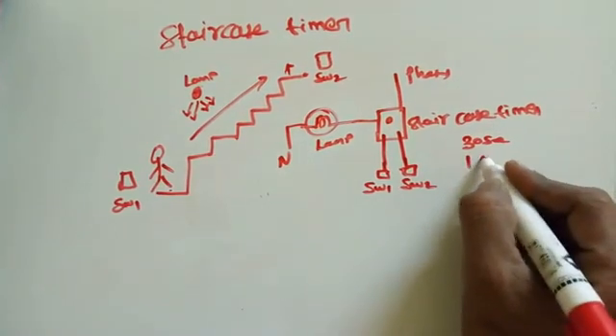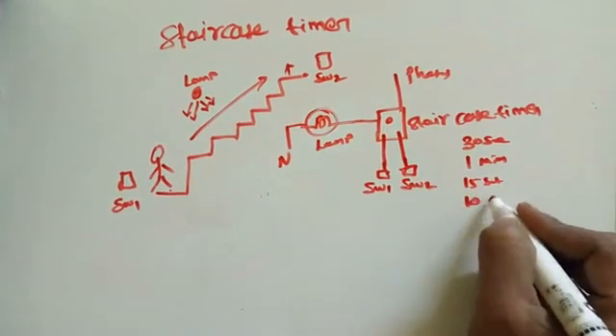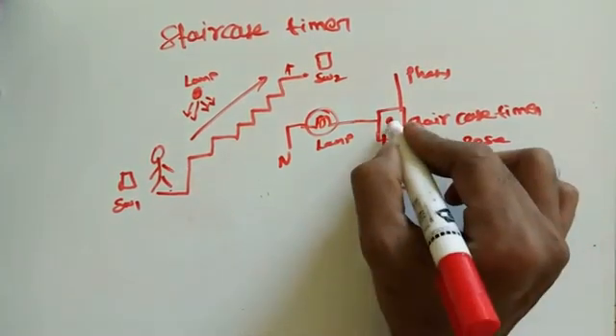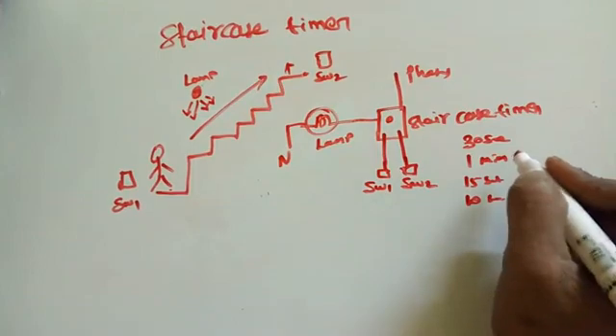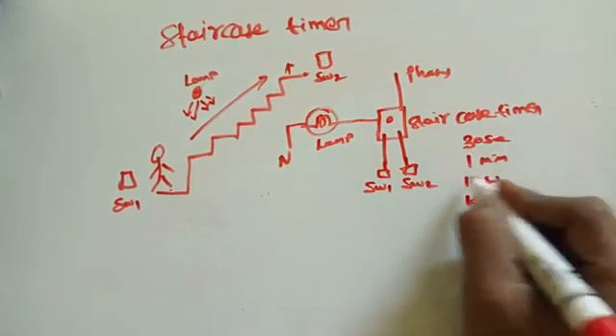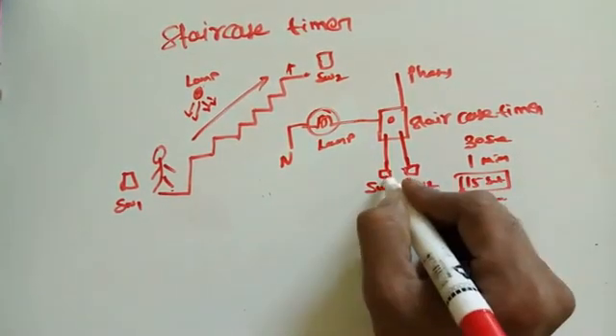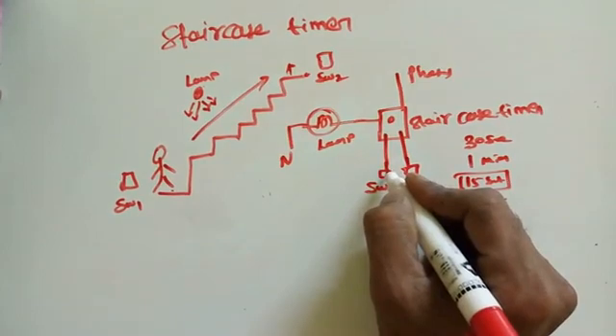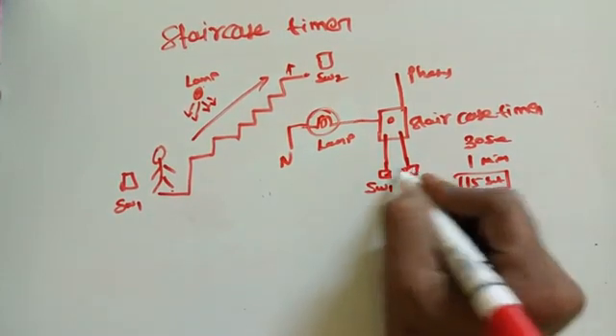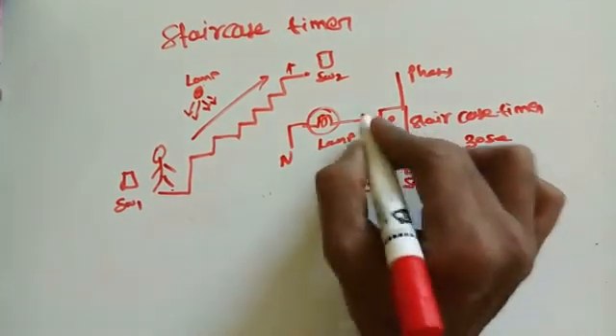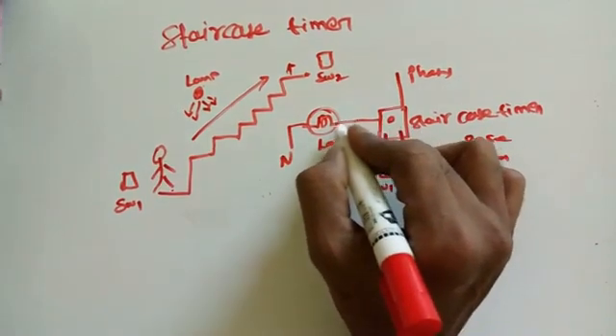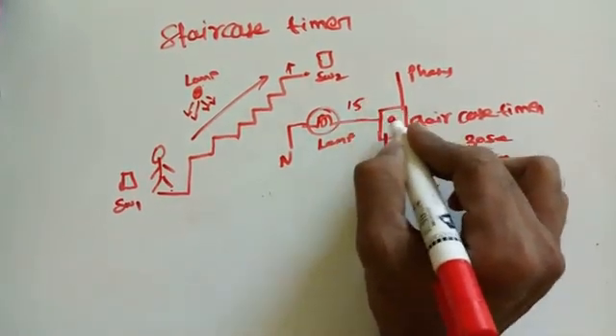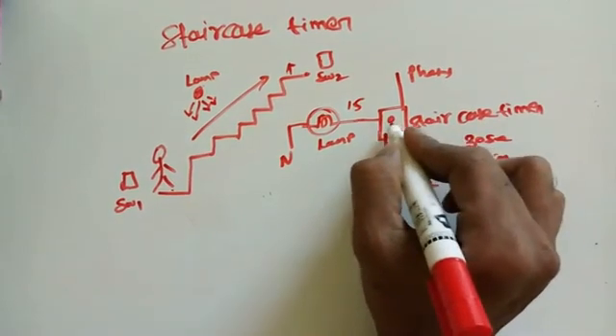One minute, or less than 15 seconds or 10 seconds - like this we set the knob. By default we set for 15 seconds. We switch on - press the switch one time here or here. Then this staircase timer gives supply to this lamp for 15 seconds.